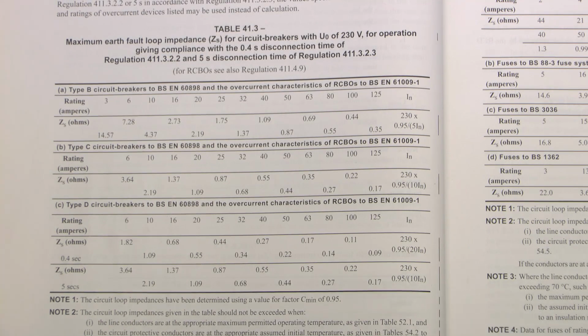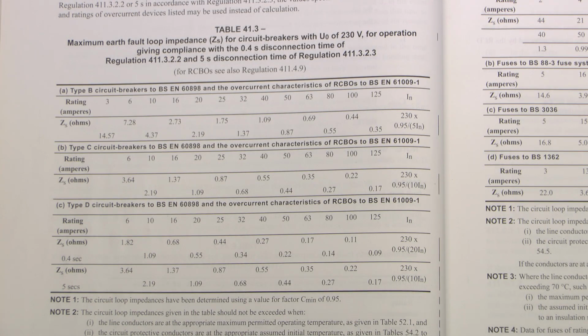Now, in terms of fitting the particular circuit breaker, before you've chosen the type B, C and D, you need to make sure that it's actually appropriate and safe to install one of these things. So what you can't do is just say, well, we've got a type C installed here, but the thing we're turning on is still tripping, so let's just shove in a type D instead.